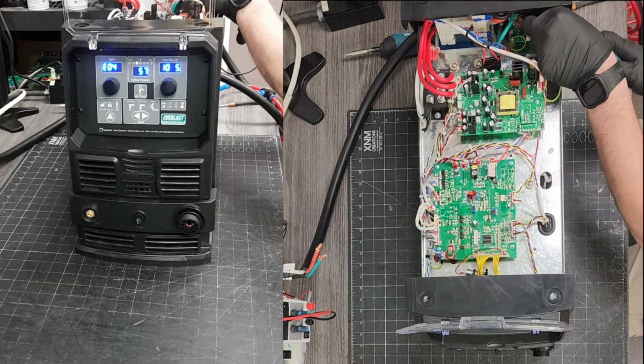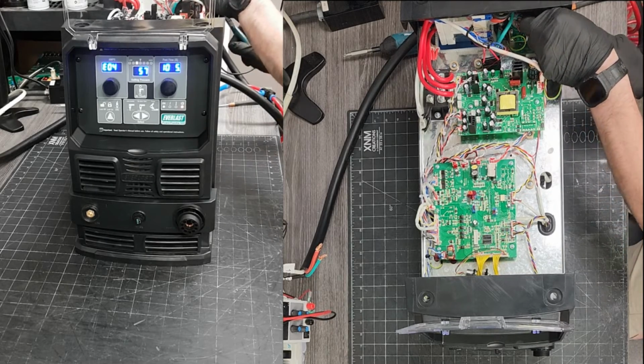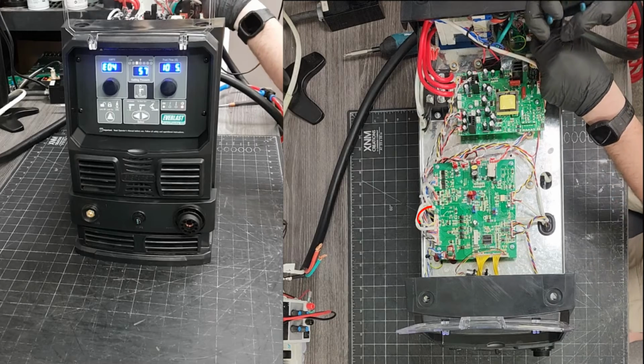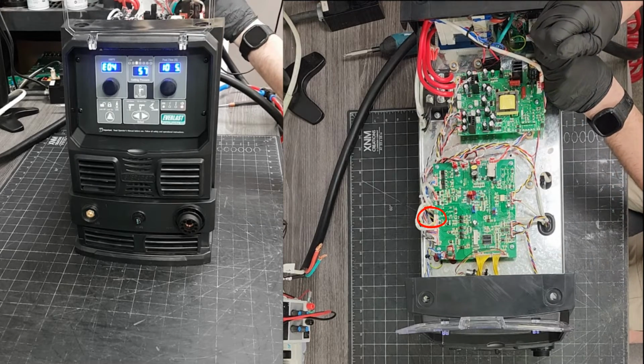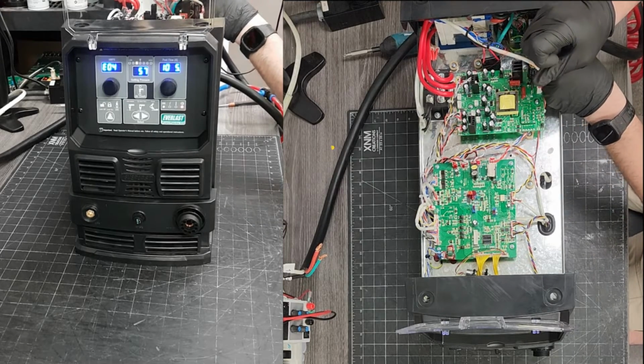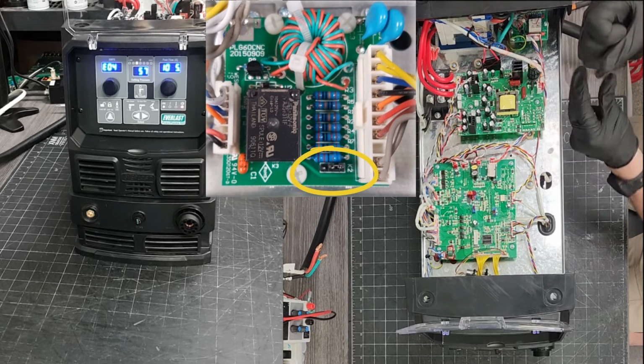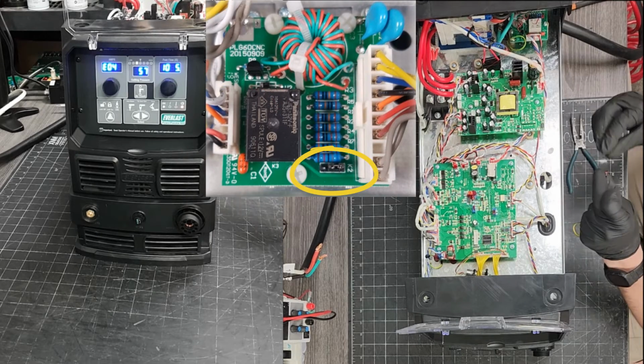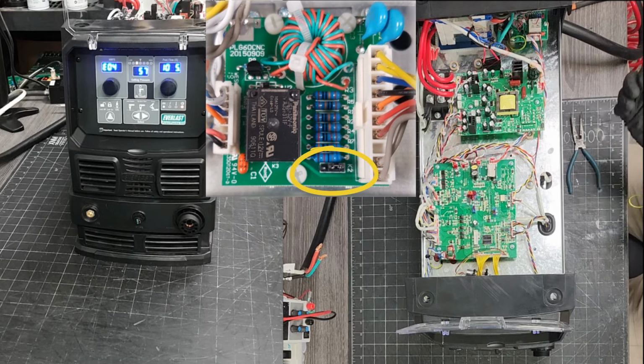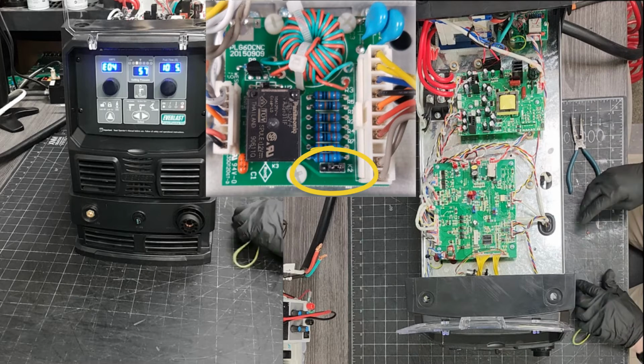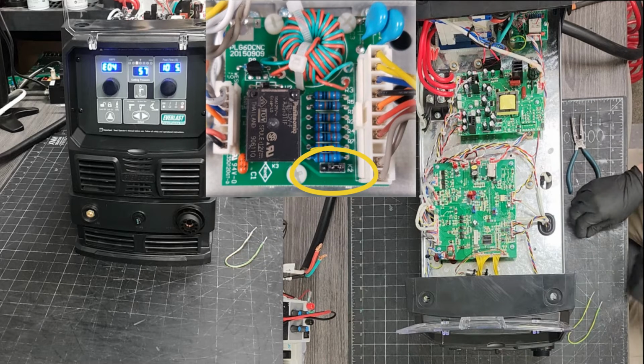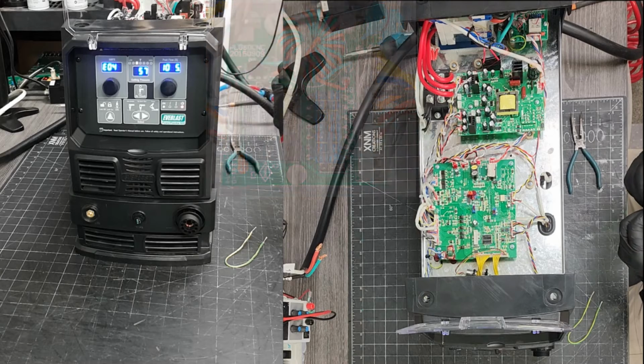If you need to bypass this feature on the machine, you'll need to short out the 2 pins in the connector J20. I like to use the voltage divider jumper on the CNC filter board, location K2, and pull the jumper off the filter board and install it into the 2-pin connector J20.